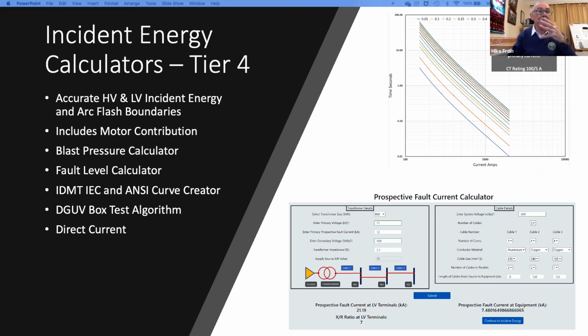There's also other tools to use to help people to get a TCC. So there's an IDMT, inverse definite minimum time, relay to IEC and ANSI standards. There's a curve creator there, so you put whether we're talking extremely inverse, the time set multiplier settings, then put against the current settings on the graph. And then there's a DGUV box test algorithm, and there's DC as well in that.